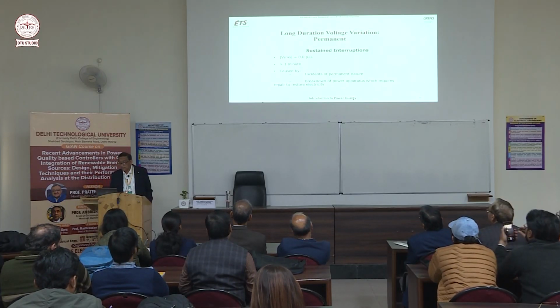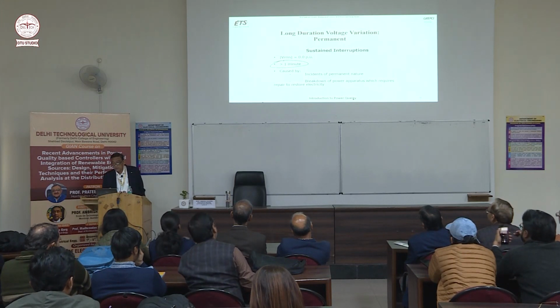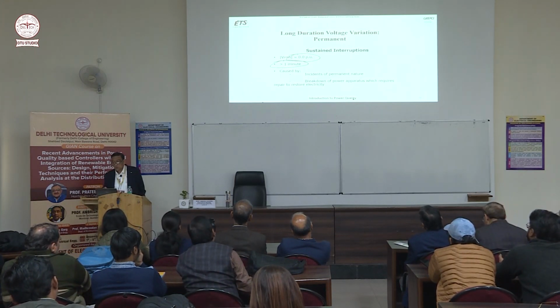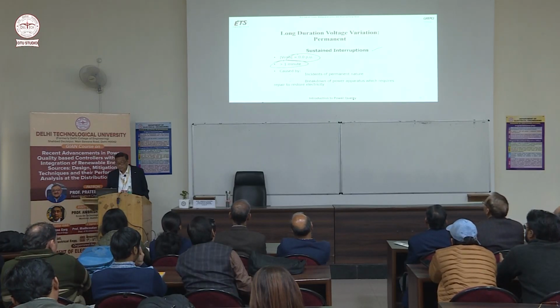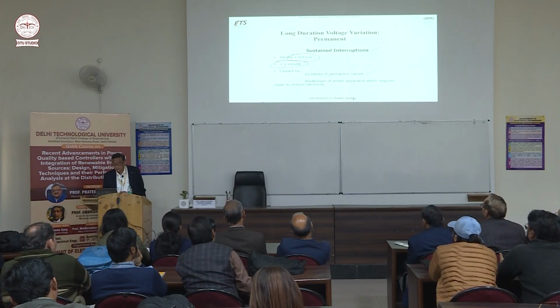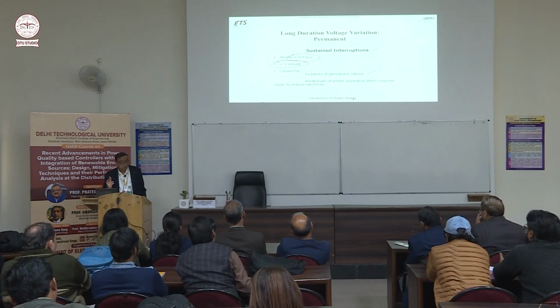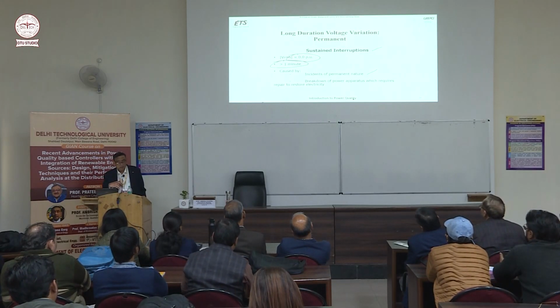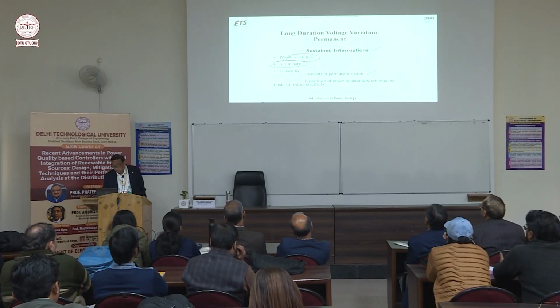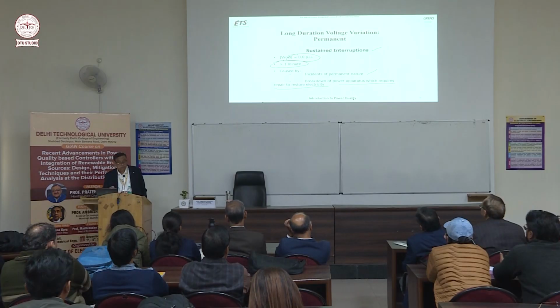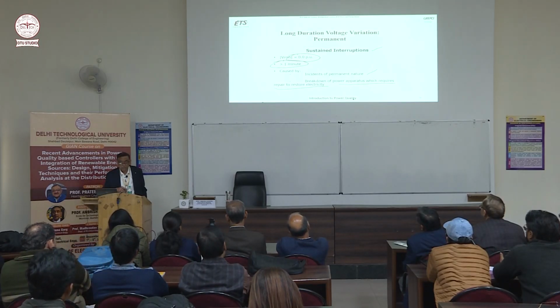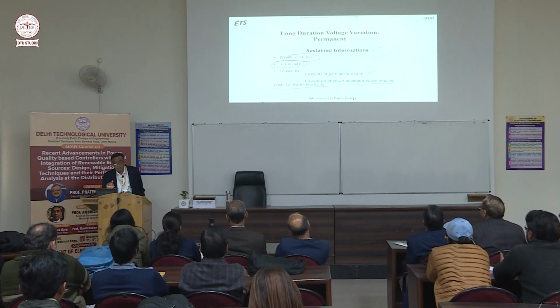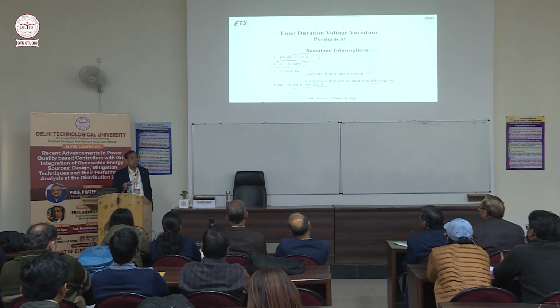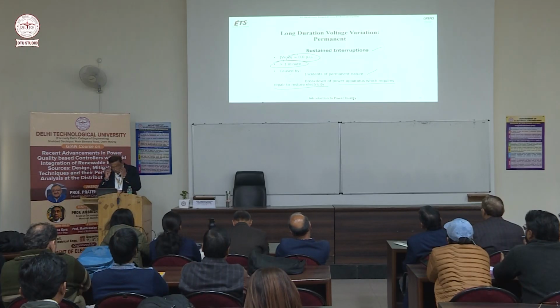Sustained interruptions: if it is more than 1 minute and your voltage is 0 pu, this is called a sustained interruption. It is caused by an incident of a permanent nature, like a storm came and a tree fell on the line, or a transformer burned out. Breakdown of power apparatus requires repair to restore, like your transformer is burned out and now it has to be replaced or repaired. So sometimes in Montreal, a Hydro-Quebec truck comes with a large transformer. Temporarily they will connect that transformer to replace this. This is what happens.